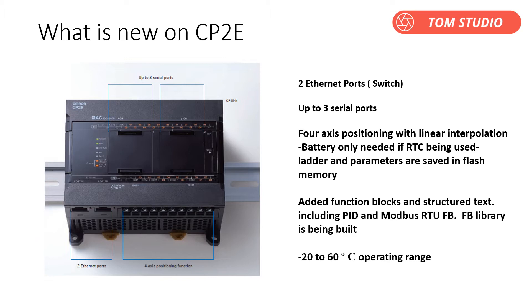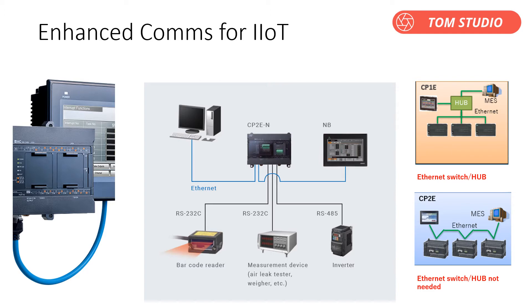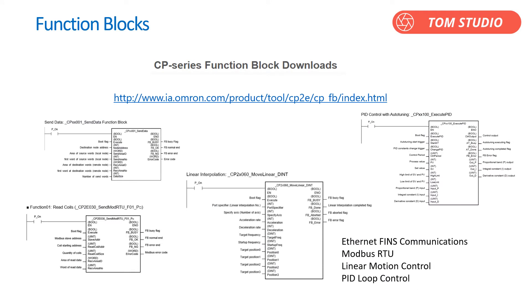The ambient temperature operating range is minus 20 to 60 degrees. CP2E comes with two built-in Ethernet ports — they are on the same network using the same IP address, so there is no need to use an Ethernet switch. Just take advantage of CP2E to easily connect to external HMIs or PLCs. Along with the CP2E new micro PLC release, Omron also released some newly designed function blocks, such as Ethernet FINS communications, Modbus RTU, linear motion control, and PID loop control.